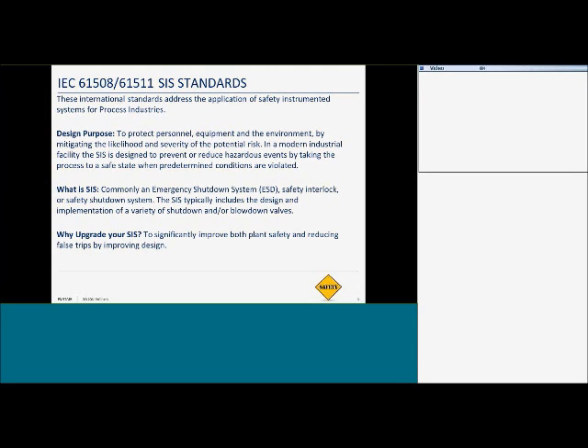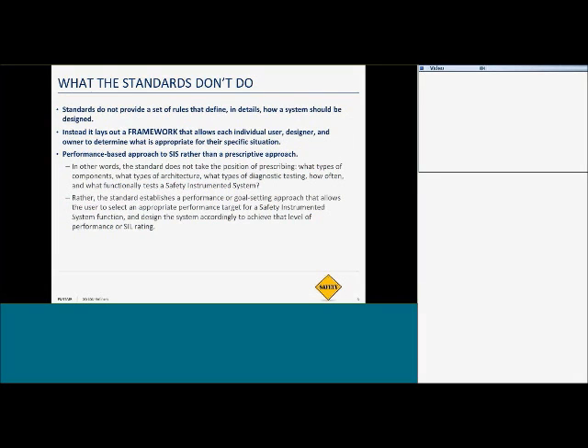So the design purposes for these was really to develop standards to protect personnel, equipment, and the environment, and mitigate the likelihood of potential risk in our plants today. They really want this system to bring a plant to a safe state if there's any sort of upset condition. So they set these limits, whether it's temperature or pressure or flow, and when any of those kinds of things are exceeded and a potentially hazardous situation is likely, then this system kicks in and it brings the plant to a safe state. It's commonly emergency shutdown or interlock safety shutdown systems, and that's really the essential part of the SIS, is to bring the plant to a safe state.